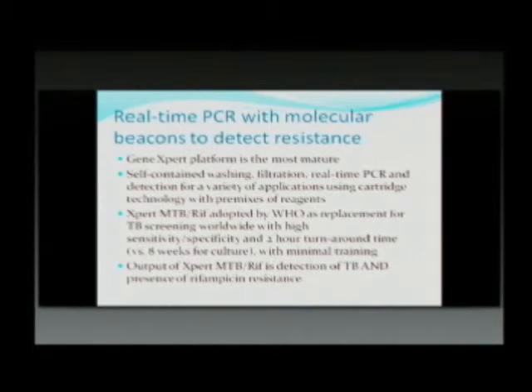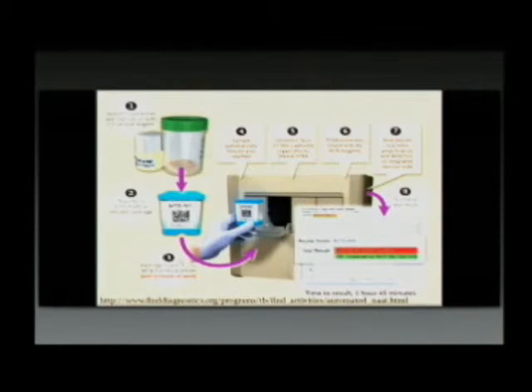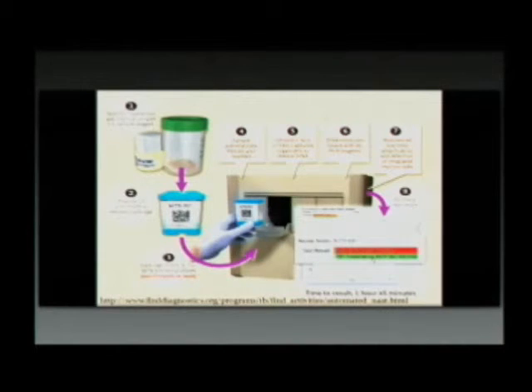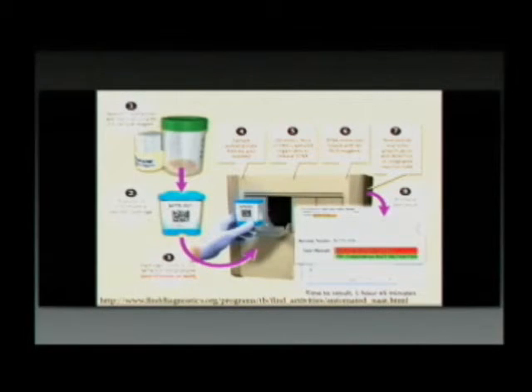The output of Xpert MTB/RIF is detection of tuberculosis and the presence of rifampicin resistance. You transfer the sputum into the cartridge — that is the end of your hands-on work. The sample is then automatically filtered, washed, extracted by ultrasonic lysis, mixed with dry PCR reagents, and detected. A typical result reads 'MTB detected, rifampicin resistance not detected.' Time to result is less than two hours — approximately one hour and 45 minutes. Because there is minimal handling of the organism, there is less risk for the lab technician, compared to growing cultures which require biosafety level 2+ facilities.